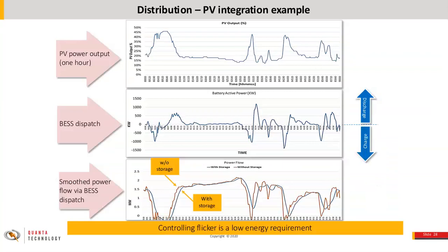Okay, so this is a PV integration example. At high PV penetration, we see two, and perhaps three, engineering problems. The first is that photovoltaic output fluctuates and can cause too much flicker on the circuit. The circuit voltage rate of change can exceed ANSI standard, and if it's too much, we get flicker, meaning customers see the lights dim.